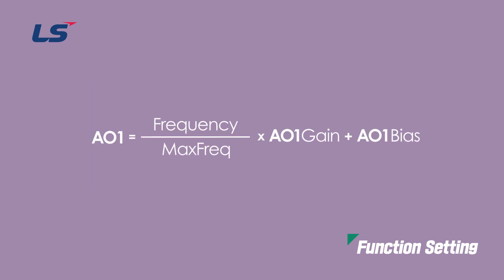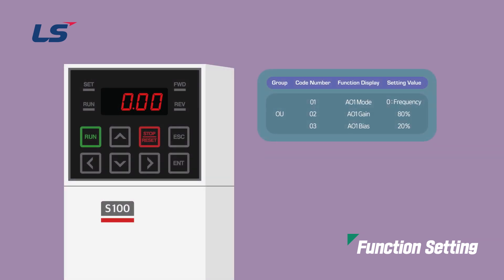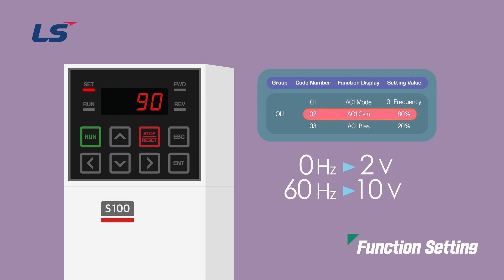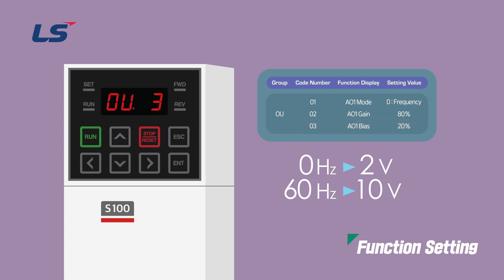Gain and bias are reflected in the output according to the formula shown on the screen. Next, we will learn how to monitor the current frequency through 2 to 10 volts output using the keypad. We will set it to output 2 volts at 0 Hz and 10 volts at 60 Hz. First, move to the OU group. Set frequency 0 in AO1 mode 1. Set the gain value for analog output to 80% in OU group number 2, AO1 gain. Set the bias value for analog output to 20% in OU group number 3, AO1 bias.